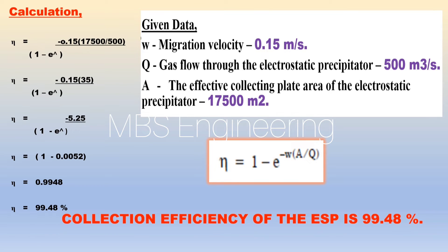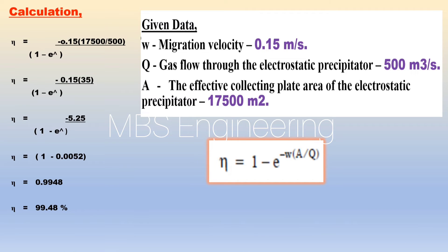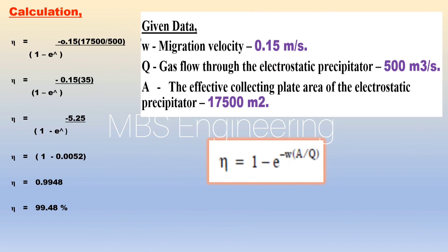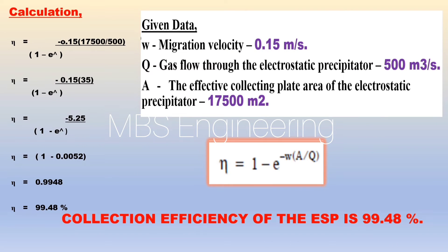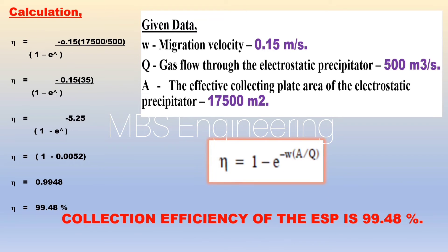As per the Deutsch-Anderson equation, the collection efficiency of the electrostatic precipitator eta equals 1 minus e to the power of minus migration velocity multiplied by effective collecting plate area divided by gas flow through the electrostatic precipitator. Please refer to the step-by-step detailed calculation for a better understanding. Based on the given data, the collection efficiency of the electrostatic precipitator is 99.48%.